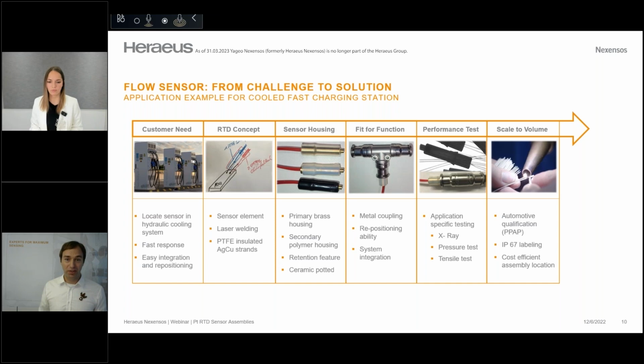Pressure test, of course, the water, the liquid coolant, is under pressure. You don't want to have the sensor popping out of that coupling. So we made a pressure test, and same direction is a tensile test. So we pulled on it to make sure that it actually withstands any kind of pull force that might occur during assembly of the equipment or later on in the process time.